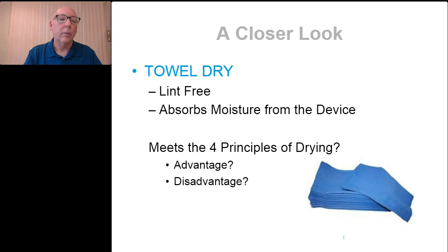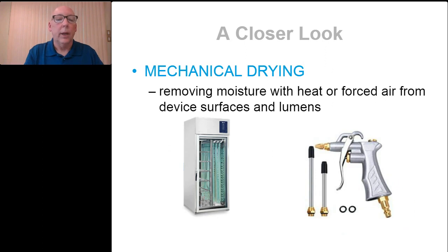Towel drying, again, also has some advantages. Simple, effective for absorbing moisture on the exterior of devices. And you do that each and every day with some of the devices that are in your department. But again, towel drying internal channels, that's just not possible, right? Because some of those ports and lumens are so small. So towel drying really is meant for the exterior of devices only. And as I mentioned, mechanical drying. Removing moisture with heat or forced air from devices and or lumens.